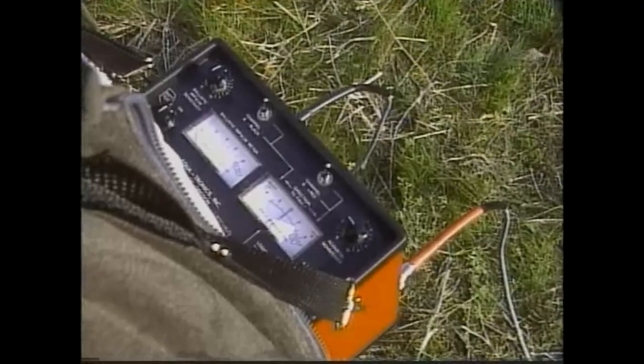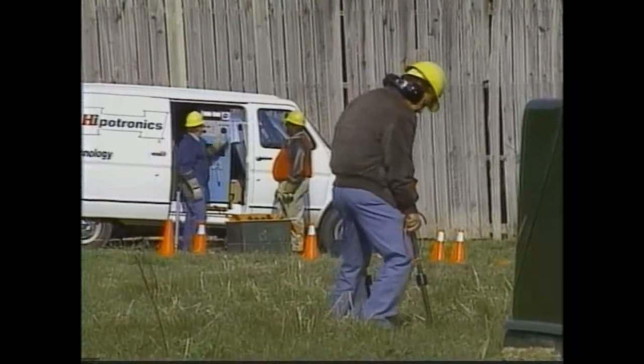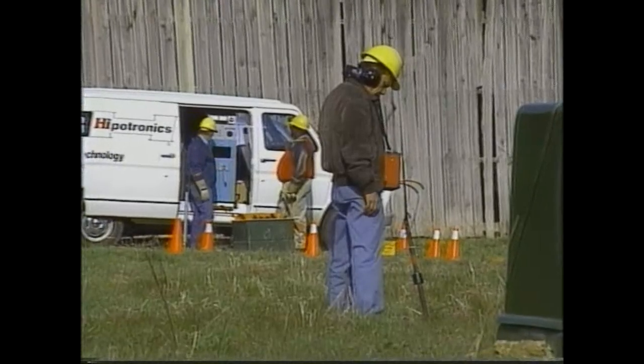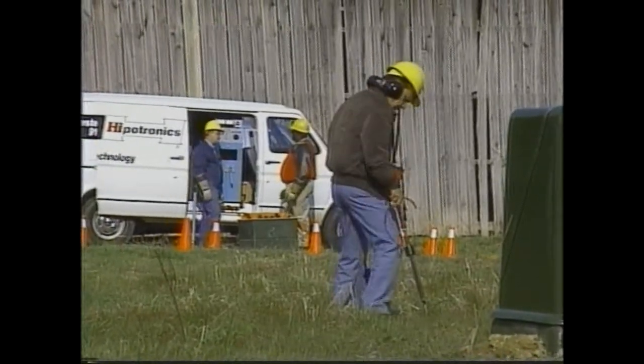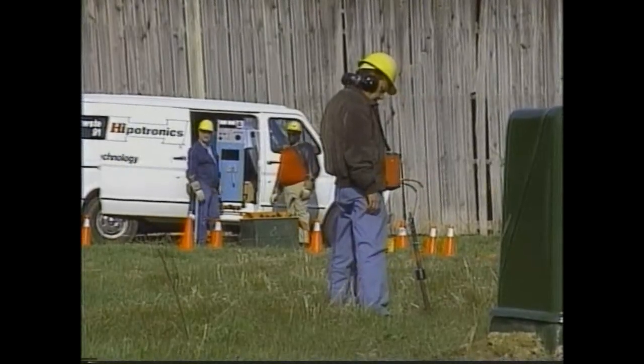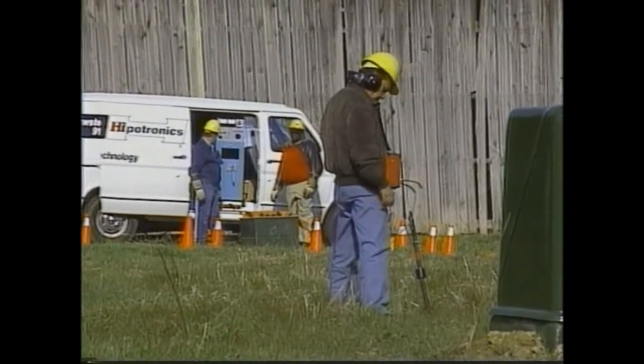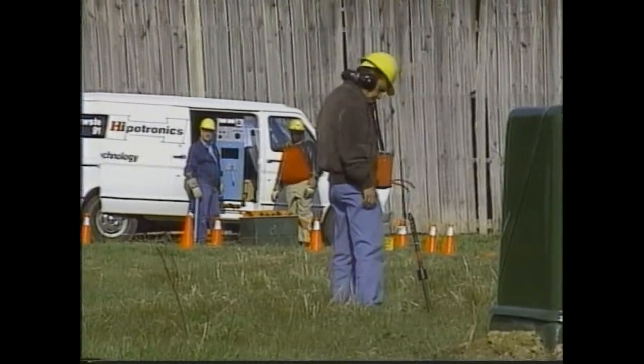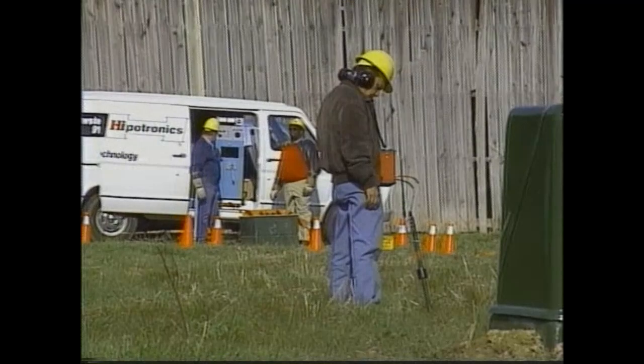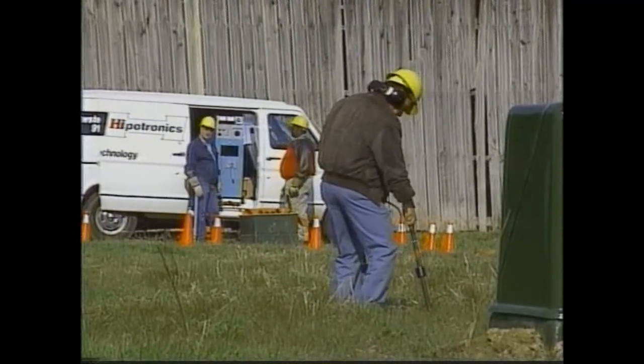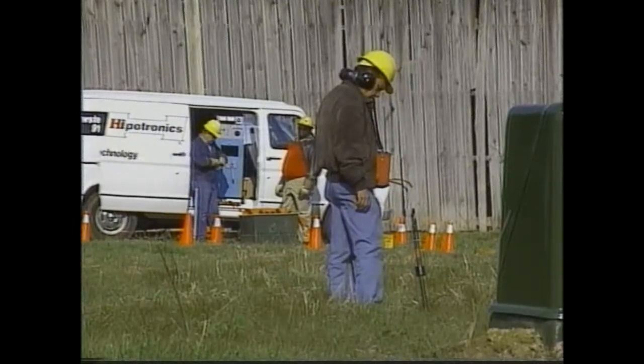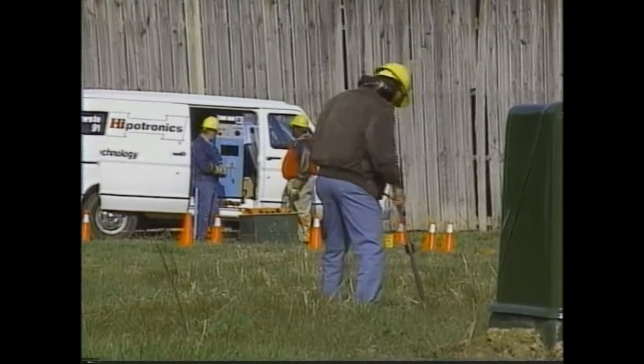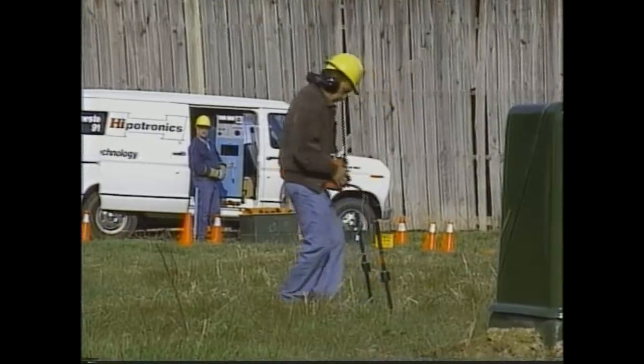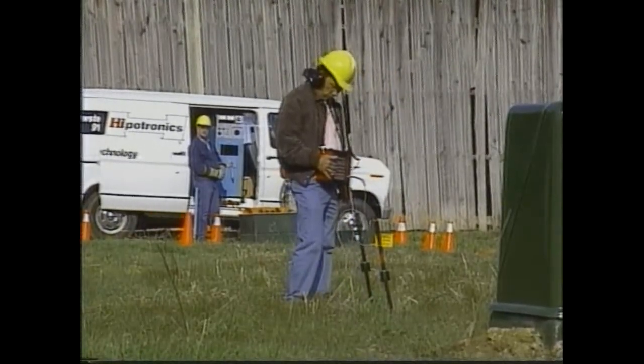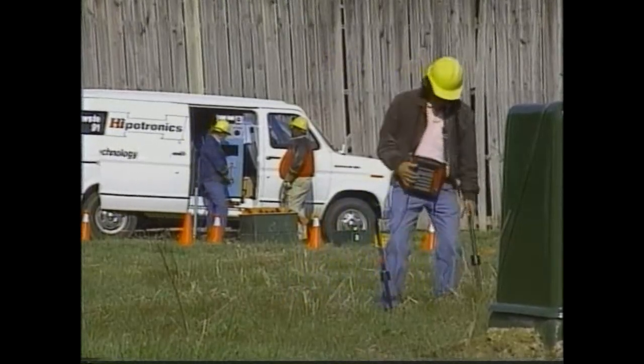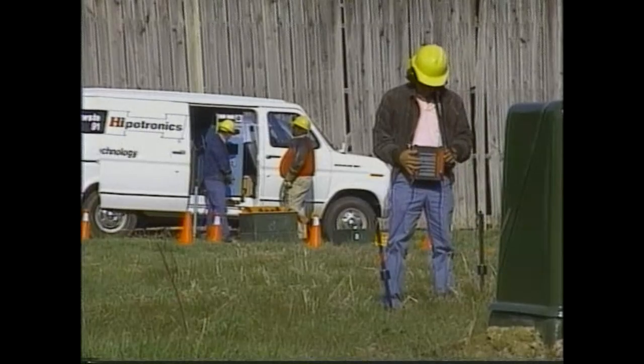Just like the earth gradient method, I now move back until my meter reverses again and trips towards the right probe. I leave the left probe alone and move the right probe away from the left probe a few inches at a time. When the meter reverses direction and trips towards the stationary or left probe, I begin to move the right or red probe closer to the other 1 inch at a time. Unlike the earth gradient detector, the logic trip meter cannot produce a null reading when it trips. It always moves either right or left. I have found a spot where 1 inch can produce a meter reversal, so I divide by 2 and mark that spot as our cable fault.